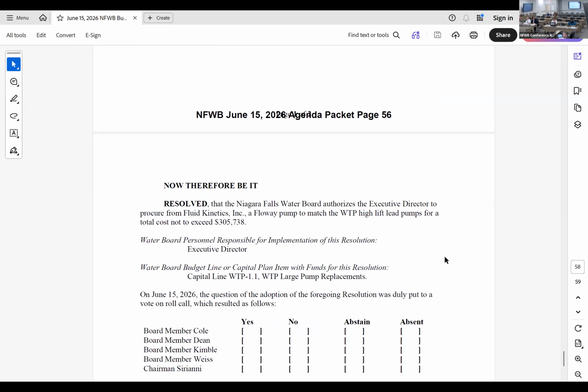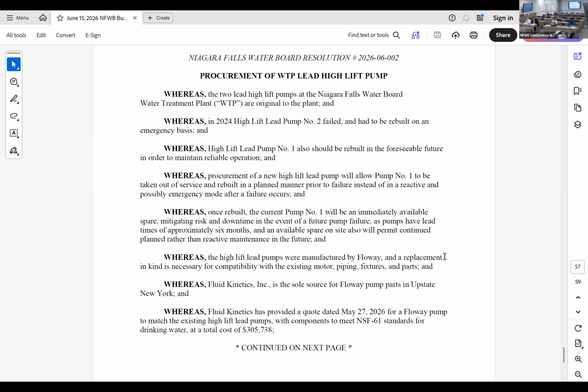Just to confirm, this is the pump we discussed before. Yes — we recently received one of two main pump sets here at the water treatment plant; there are high lift pumps and low lift pumps. The low lift pumps have two leads and four lags. We recently acquired a new lead pump in case one of the two leads fails, since both leads have been in service since the plant went online and have never been rebuilt. This gives assurance that if something happens, we can plug that pump in. We'll have similar capability with the lead high lift pumps once this new pump arrives. In 2024, one of the high lift pumps was rebuilt, so this will give us a spare, letting us be proactive rather than reactive in maintenance.